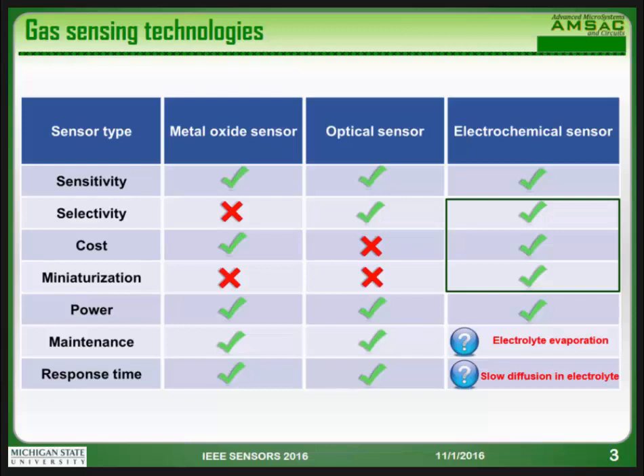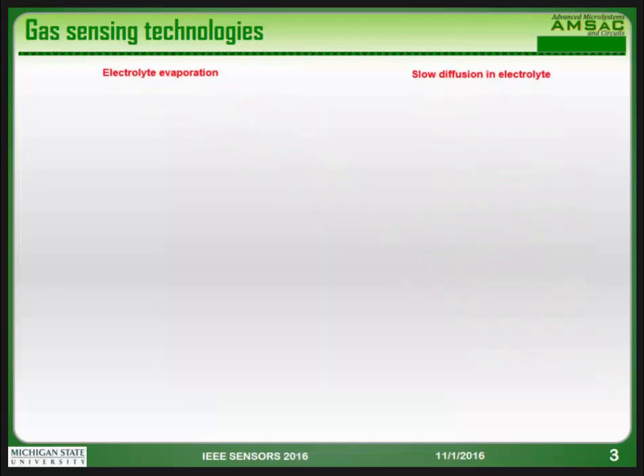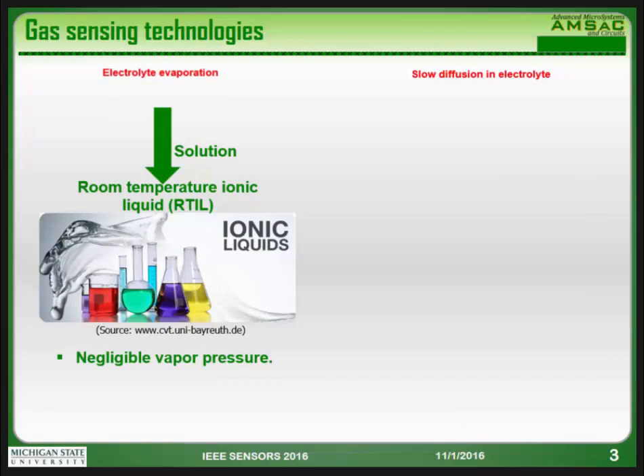But the electrochemical sensor has its intrinsic drawbacks, which is the maintenance. Because when we use the electrochemical sensor, we need an electrolyte, and the liquid electrolyte very easily evaporates, so we need frequent maintenance. And the other thing is the response time: the gas needs to diffuse through the electrolyte, and the diffusion coefficient is very low, so it will take a long time. For these two problems, we came up with some solutions.